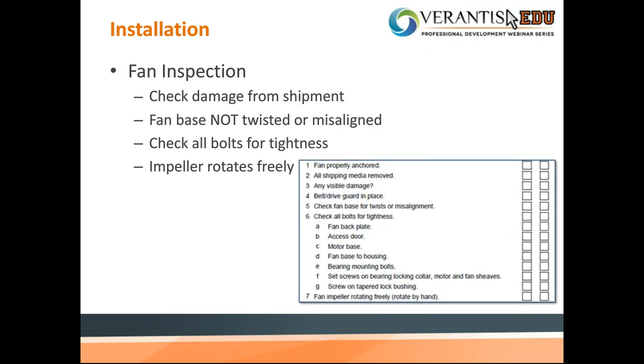So, all right, with fan inspection, you've checked the fan for damage during shipment. Make sure the base is not twisted or misaligned. Check all the bolts for tightness, and make sure the impeller rotates freely. So it's basically taking all of your shipping and receiving inspections to the next level. Yeah, the fan OEMs, we keep all of our bolts tightened, but some stuff breaks free during shipment, and it's worth just making sure all of that stuff is checked out accordingly.